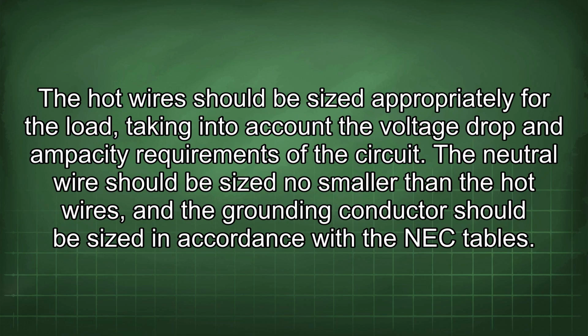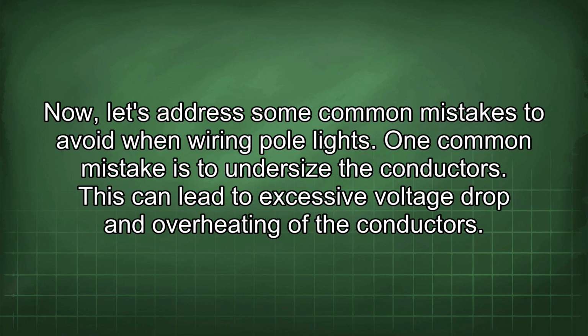The hot wires should be sized appropriately for the load, taking into account the voltage drop and ampacity requirements of the circuit. The neutral wire should be sized no smaller than the hot wires, and the grounding conductor should be sized in accordance with the NEC tables. Now let's address some common mistakes to avoid when wiring pole lights.